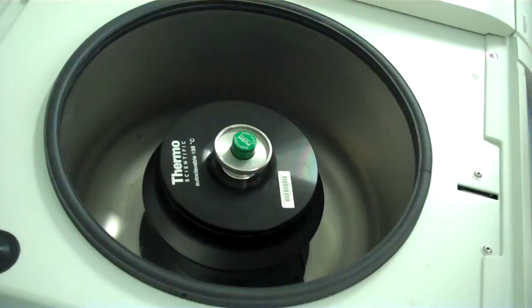Now this is the only rotor that actually has a lid, and you have to put the lid on after you place in your tubes. So you put the lid on, and even though you see this thing that says push, don't push. This is actually for removing an entire rotor. Instead, you put on the lid and you hold on to the rotor itself a little bit as you turn the top of the lid clockwise, and it should go easily. If it's not going relatively easily, it means that it's threaded wrong and you need to start over. Once you have the top on, now it is ready to centrifuge.